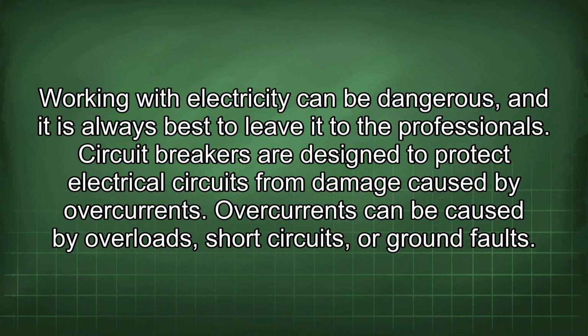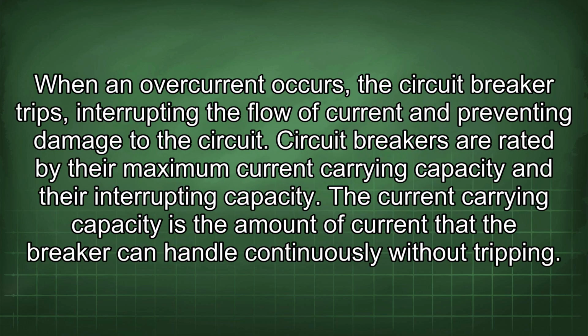Circuit breakers are designed to protect electrical circuits from damage caused by overcurrents. Overcurrents can be caused by overloads, short circuits, or ground faults. When an overcurrent occurs, the circuit breaker trips, interrupting the flow of current and preventing damage to the circuit.